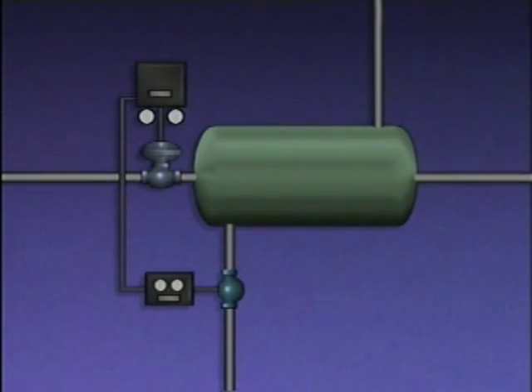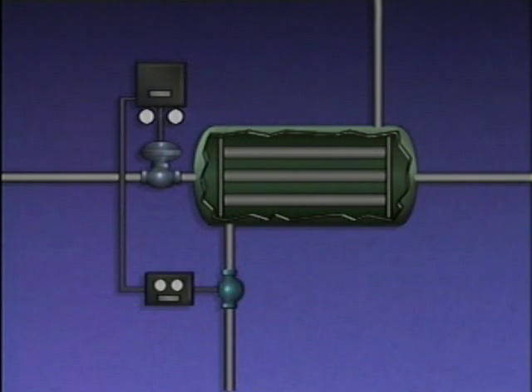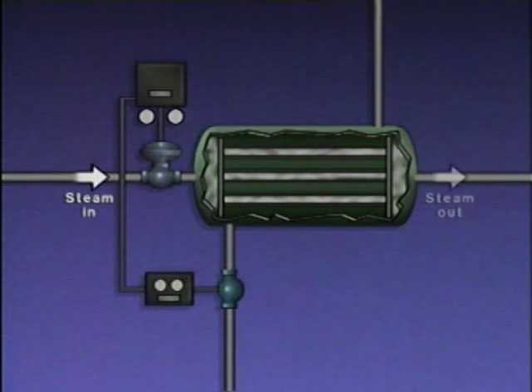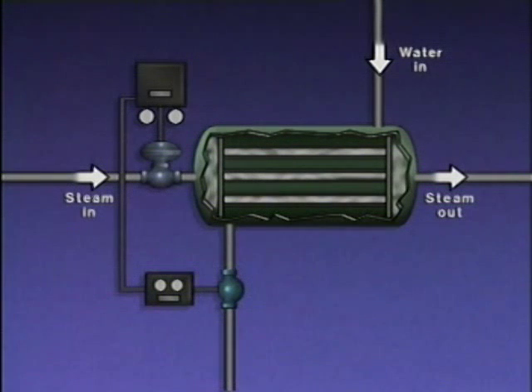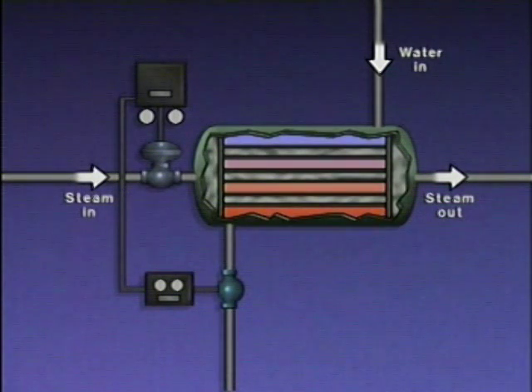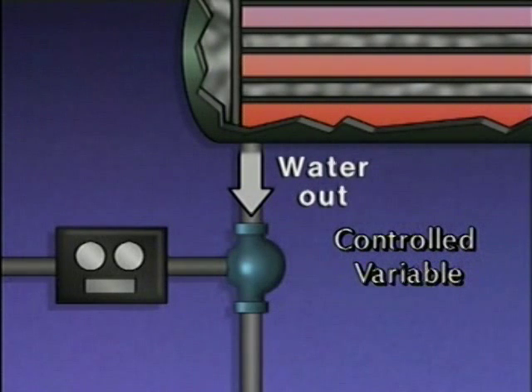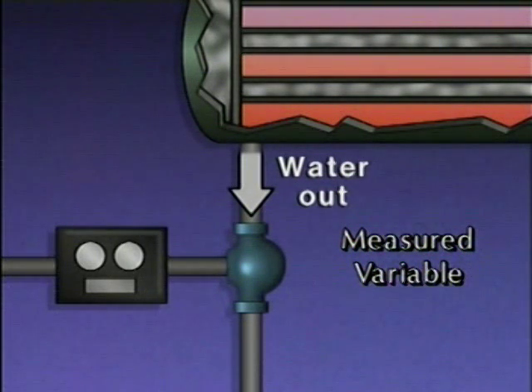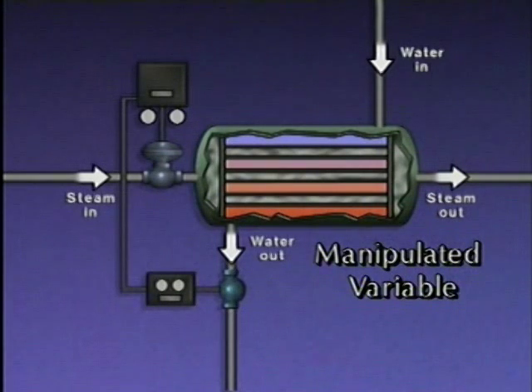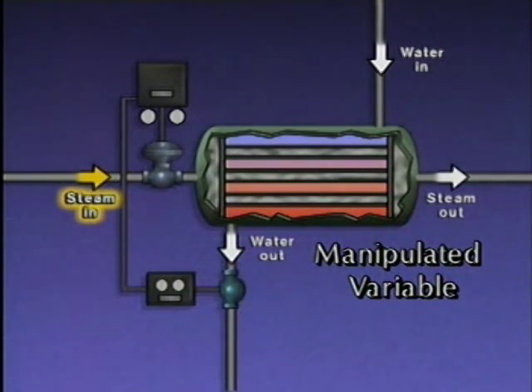To see how an automatic feedback control system works, we'll use this illustration of a heat exchange process. In this system, steam is used to heat water. The steam enters the system through a valve, then flows through tubes inside the heater and exits through a pipe on the other side. The steam transfers heat to the water, which enters the heater at the top, flows around the tubes, and exits the heater at the bottom. The temperature of the water at the outlet of the heater is the controlled variable for the system. It's also the measured variable, because the control system uses it as a basis for making operating changes. The manipulated variable in this system is the inlet steam flow, which is adjusted to keep the outlet water temperature at set point.